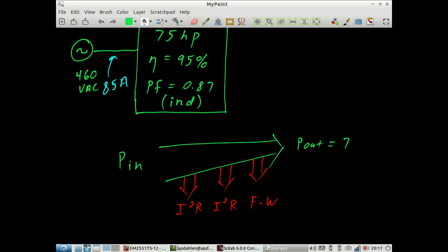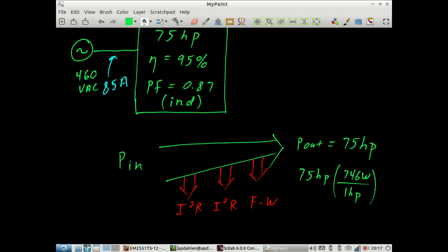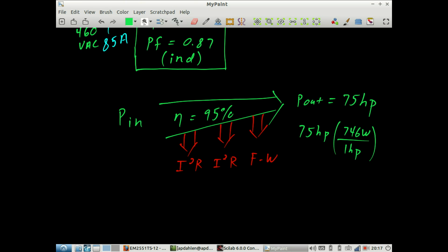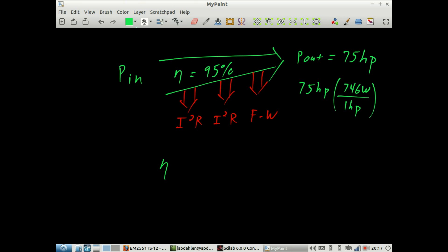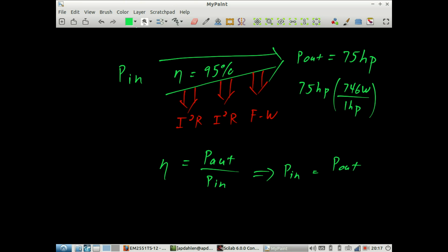The power out of this motor is 75 horsepower. We'll need to do a conversion where we take 75 horsepower and convert it to watts, recalling that one horsepower is equal to 746 watts. The efficiency of this motor is given as 95%, which means that 95% of the power in ends as power out, and 5% ends up in these various losses. We can write that efficiency equals power out over power in, and it follows that power in equals power out over efficiency.